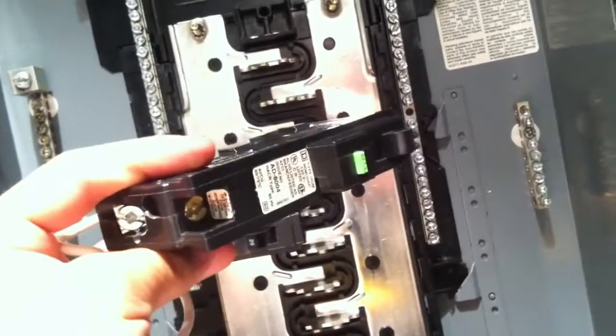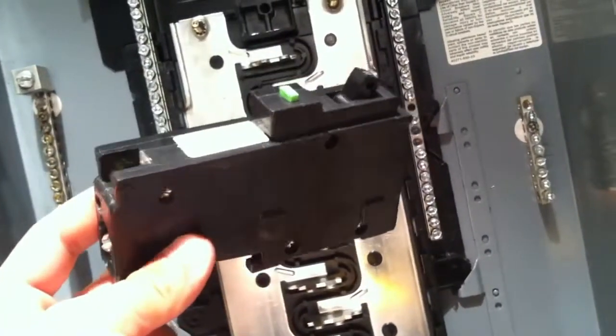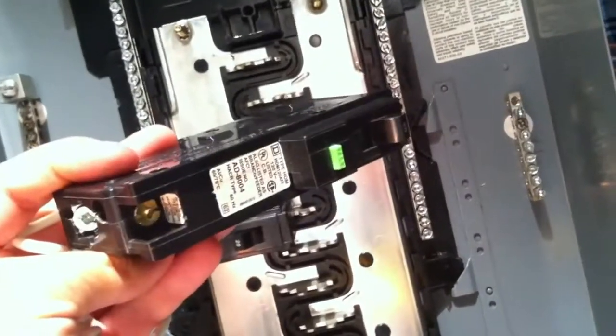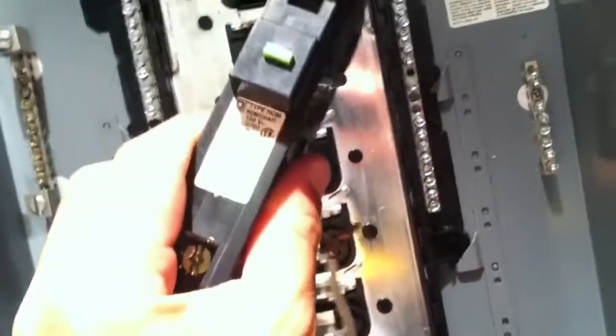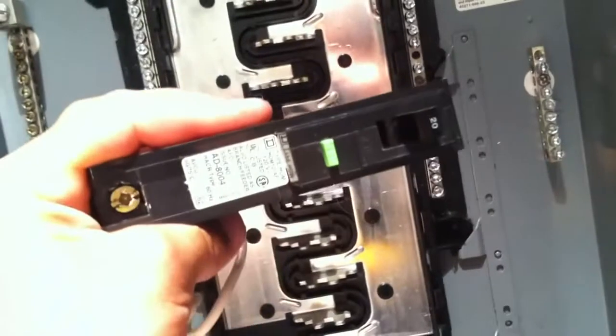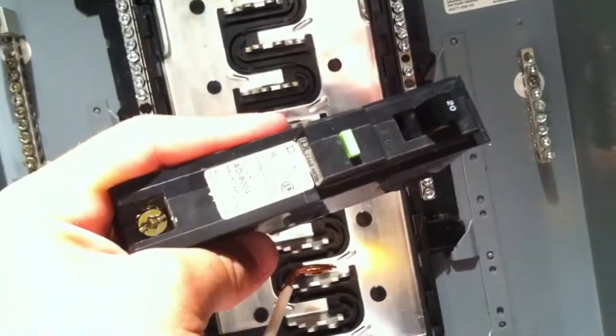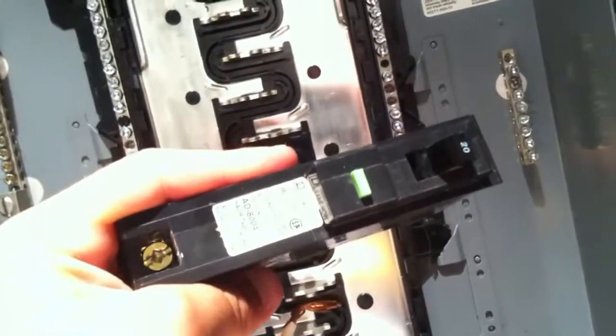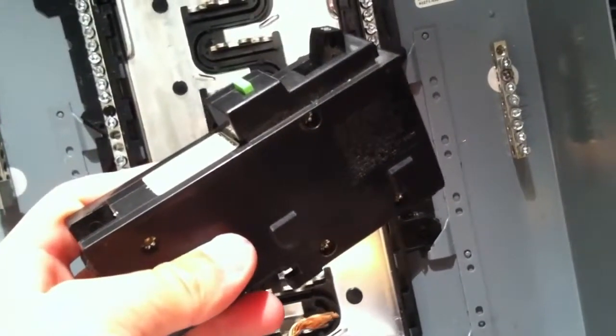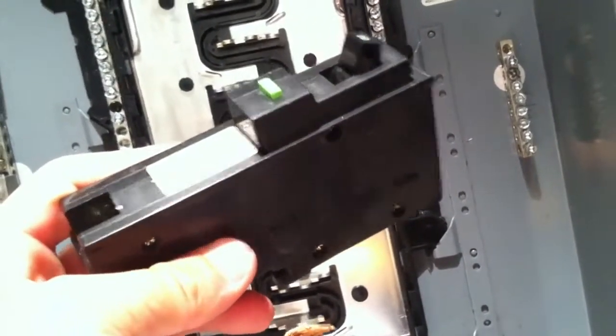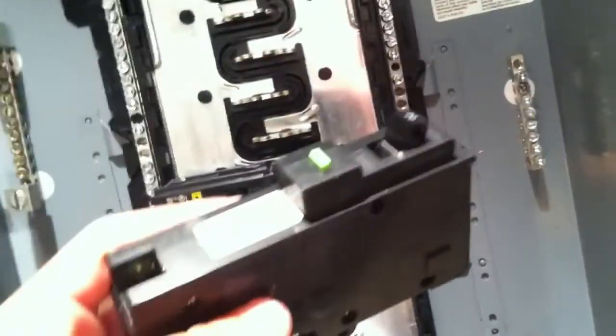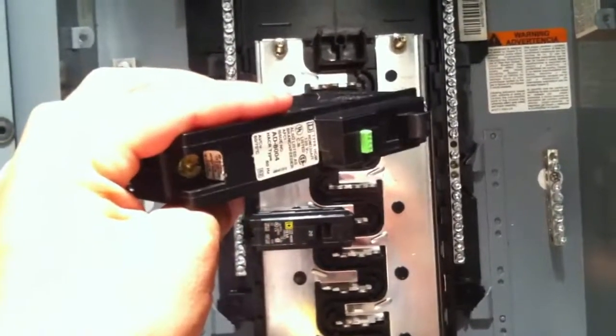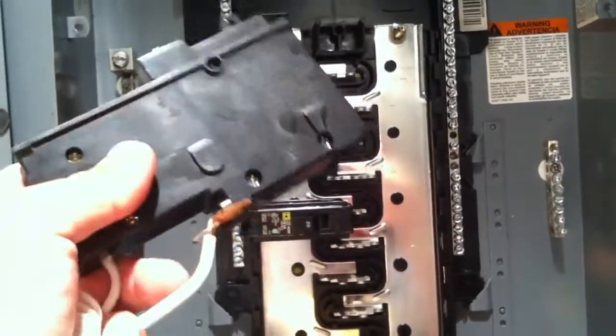Okay, these breakers monitor the neutral line. So here's what these things do. There's AFCI and there's GFCI. AFCI stands for arc fault circuit protection. GFCI stands for ground fault circuit protection. This basically just detects to make sure that there are no arcs going on in the circuit. It also detects ground faults, where there's water. So if there's a bathtub or something, it makes sure that there's no electricity flowing through water or grounded circuits. If there is, it'll instantly shut off.